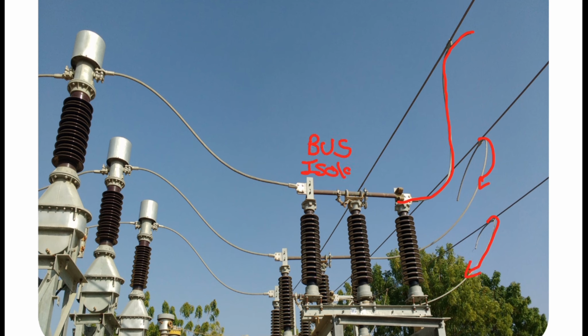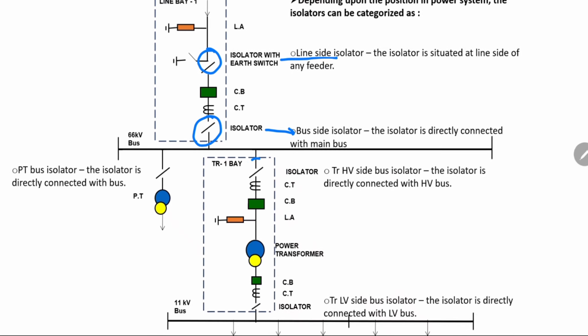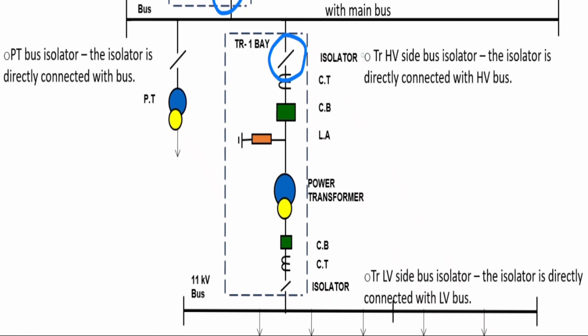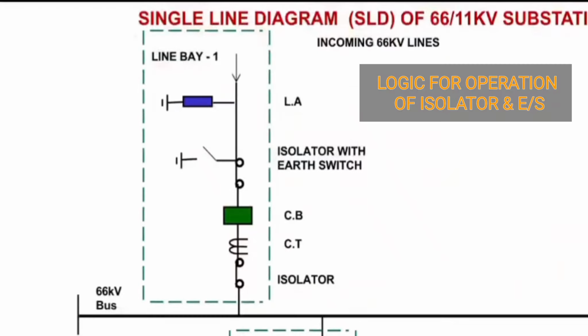Coming back to our SLD, now let us focus on the TR bay. Here, the isolator connected on the high voltage side of the bus is called the TR HV side bus isolator, and the isolator connected on the low voltage bus side is called the TR LV side bus isolator. Also, for the PT, its isolator connected directly with the bus is called the PT bus isolator. Let us see the logic behind the operation of isolators and earth switches. Consider that the 66 kV bus is charged, which is shown by the red line. Also, the line bay is charged and it is also shown by the red line, as shown here.